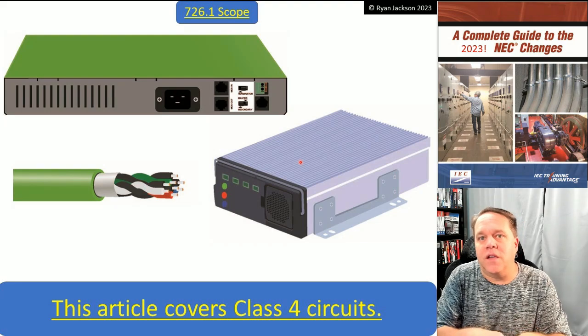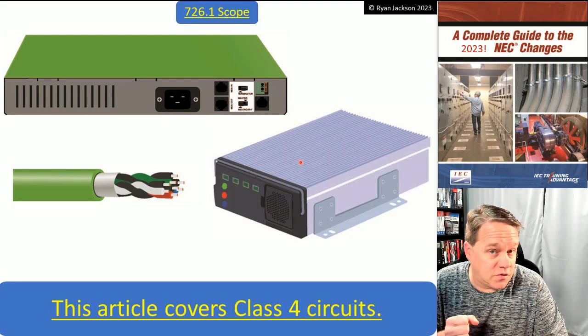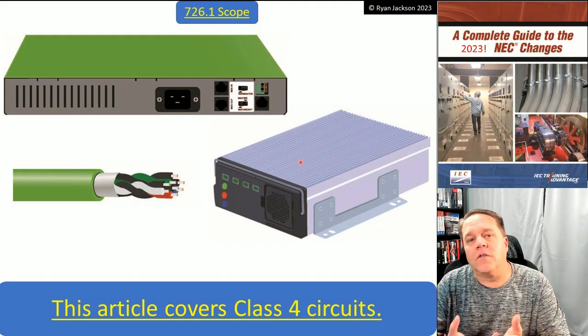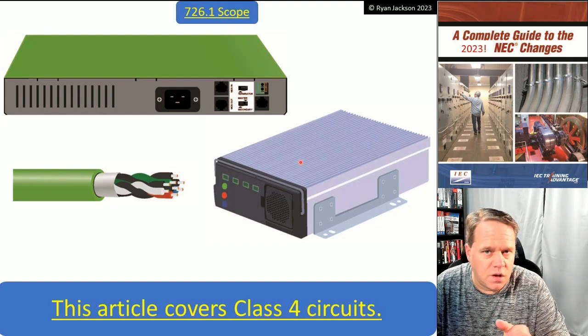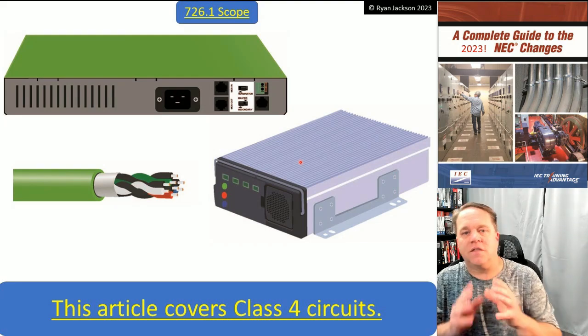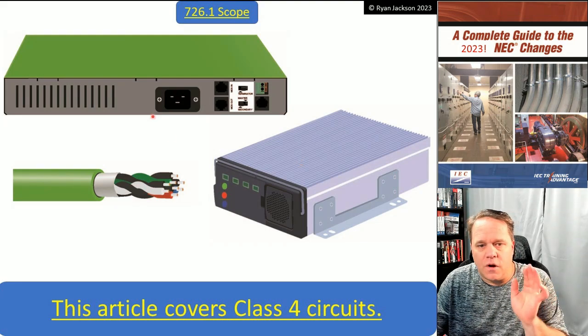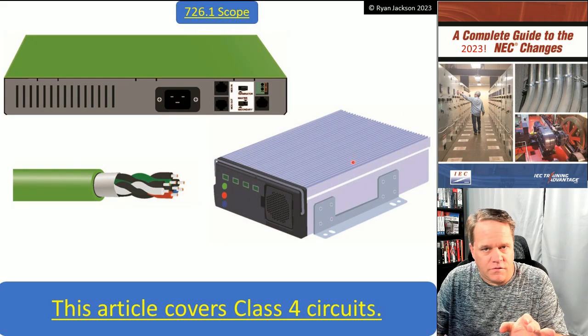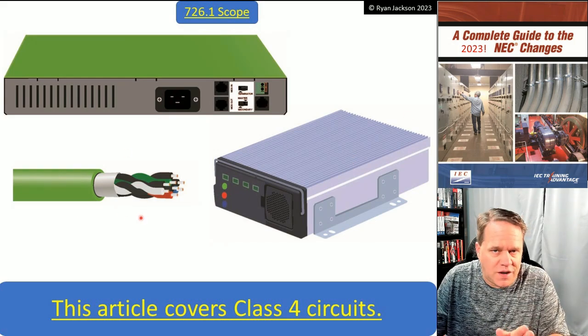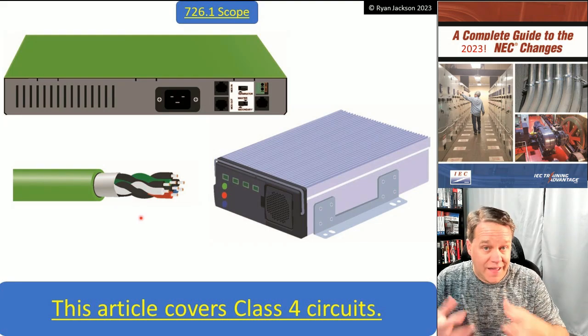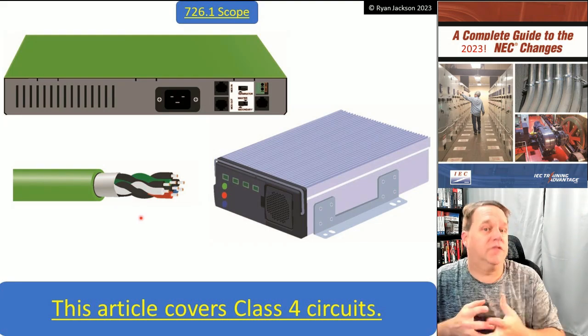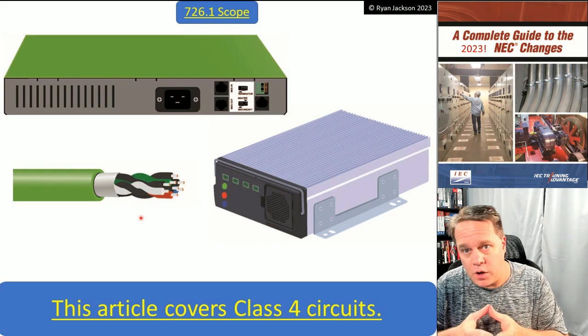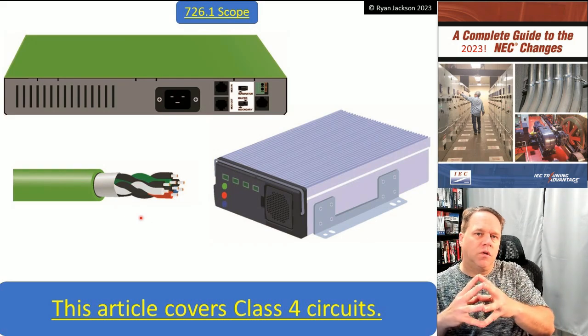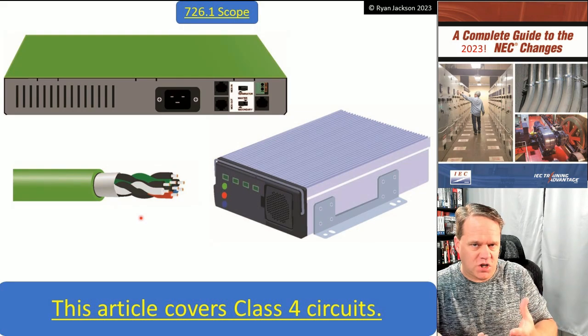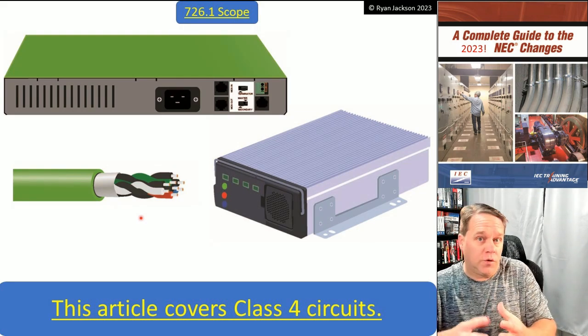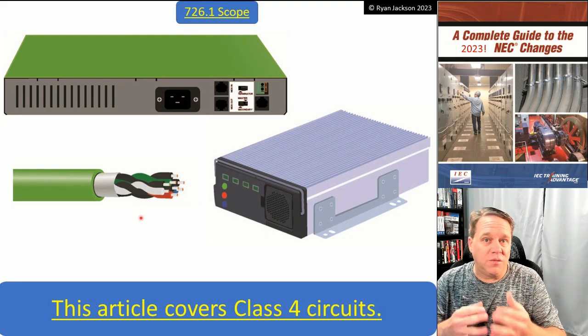With Class 4, I can get much higher voltages, 450 volts peak, and I can get higher levels of current on a Class 4 circuit. So how is that safe? Well, it's safe by the technology. It comes from a transmitter and it ends at a receiver, and it uses a Class 4 cable. Belden has a listed Class 4 cable now. To the best of my knowledge, they're the only ones right now that have the product. But the way this works is it works on the concept of using a handshake, which is, if you're really into low voltage or computers, networking, that should be familiar to you.